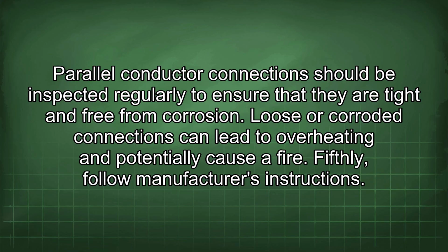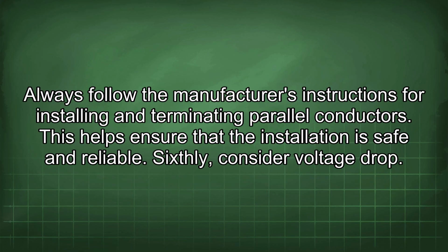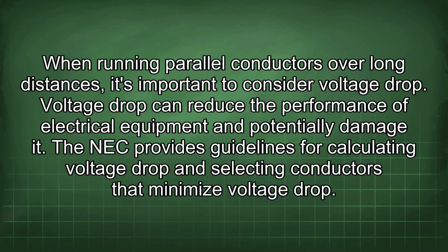Fifthly, follow manufacturer's instructions. Always follow the manufacturer's instructions for installing and terminating parallel conductors. This helps ensure that the installation is safe and reliable. Sixthly, consider voltage drop. When running parallel conductors over long distances, it's important to consider voltage drop. Voltage drop can reduce the performance of electrical equipment and potentially damage it. The NEC provides guidelines for calculating voltage drop and selecting conductors that minimize voltage drop.